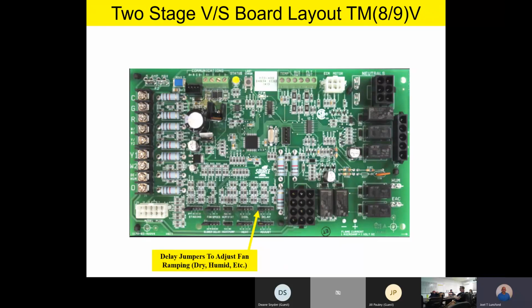So A is normal. A comes from the factory. A is normal, and what that does is ramp the fan up. I don't remember them all exactly, but let's just say in the normal mode of operation, it takes 1.5 minutes to ramp the fan up to 100%, and then 1.5 minutes to ramp it down. In the B profile, that's a humid profile. We just talked a little bit about that, a nice delay on the front to get a lot of moisture out of the air. I think the C profile is what we call a dry profile.